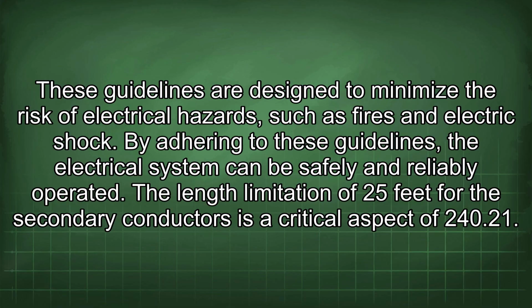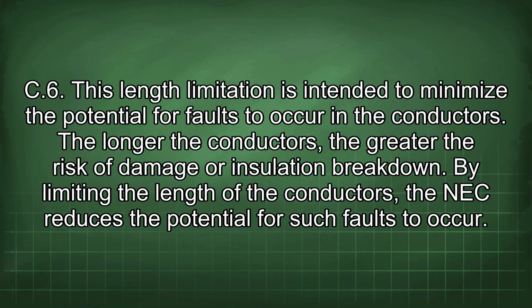The length limitation of 25 feet for the secondary conductors is a critical aspect of 240.21(C)(6). This length limitation is intended to minimize the potential for faults to occur in the conductors. The longer the conductors, the greater the risk of damage or insulation breakdown. By limiting the length of the conductors, the NEC reduces the potential for such faults to occur.